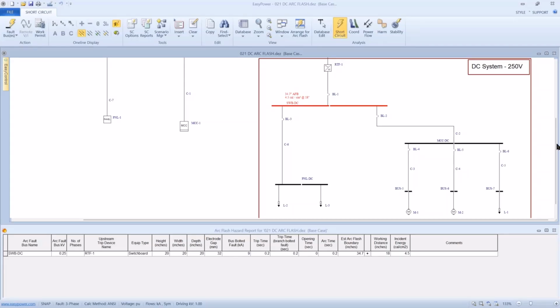So in the tables that we talk about in IEEE, they do not have an upper limit as long as our PPE rating is equal to or exceeds the calculated incident energy for a particular bus. So the answer to your question is, I'd be real careful, but I would choose any other way before I go that route, and make sure I had plenty of room to exit the area.